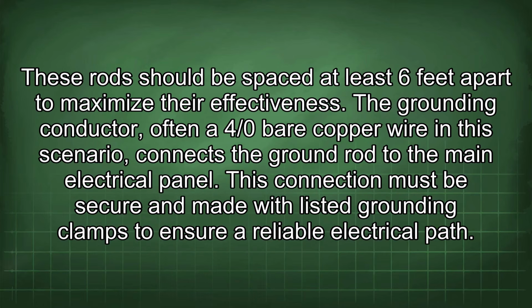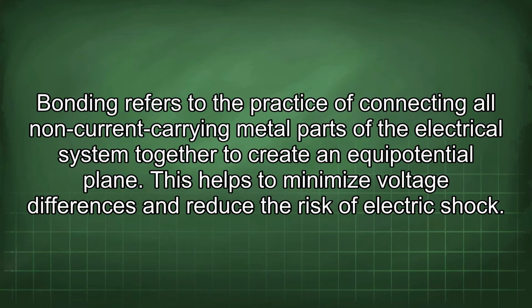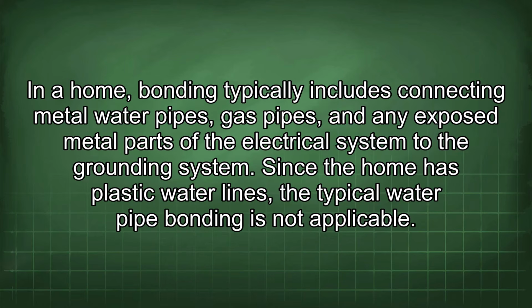The grounding conductor, often a 4/0 bare copper wire in this scenario, connects the ground rod to the main electrical panel. This connection must be secure and made with listed grounding clamps to ensure a reliable electrical path. Bonding refers to the practice of connecting all non-current carrying metal parts of the electrical system together to create an equipotential plane. This helps to minimize voltage differences and reduce the risk of electric shock. In a home, bonding typically includes connecting metal water pipes, gas pipes, and any exposed metal parts of the electrical system to the grounding system.